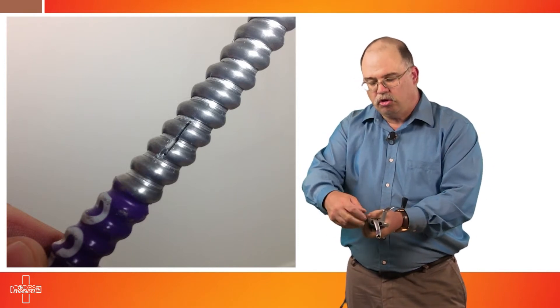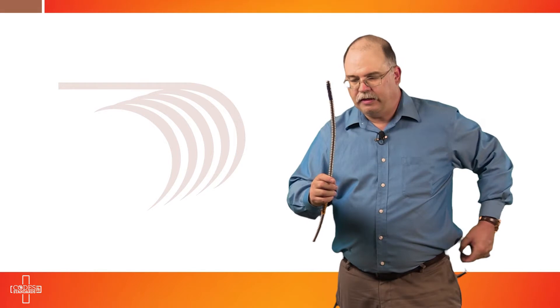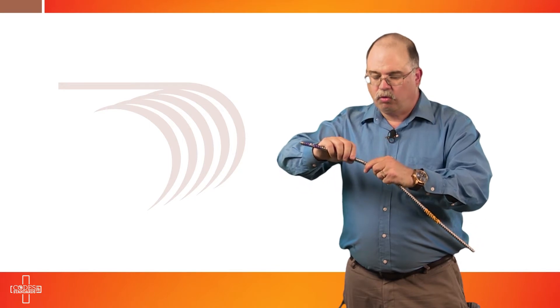At that point, you'll loosen the set screw, pull the Type MC Smart Ground product out of the device, and you'll notice you have a cut here. You want to twist the metallic sheathing in a counterclockwise way and then slowly remove the metallic sheathing from the cable.